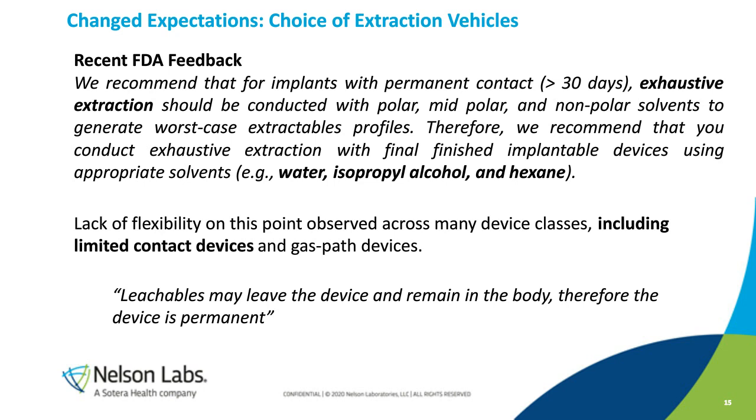I think that for anything that's prolonged or permanent, you should anticipate at least attempting 3 solvents, a polar, midpolar, and nonpolar. And then if for some reason you want to exclude one of those solvents or one solvent is not compatible, you really should be prepared to provide a rigorous scientific justification on why you're not using that.